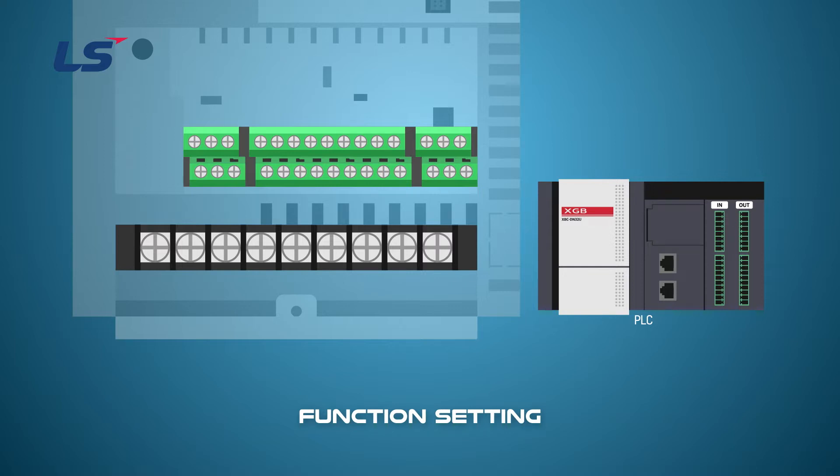Since the lift is a device that moves up and down, the forward and reverse terminal connections are required. Connect to P1 and P2. P1 is forward direction, and P2 is reverse direction.